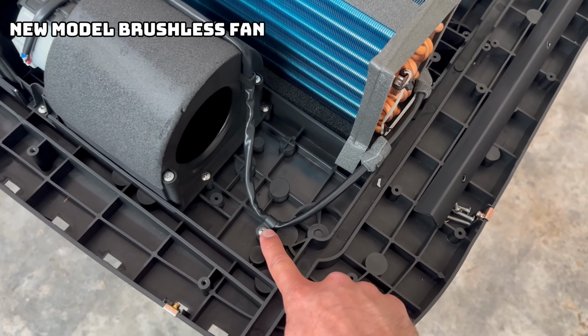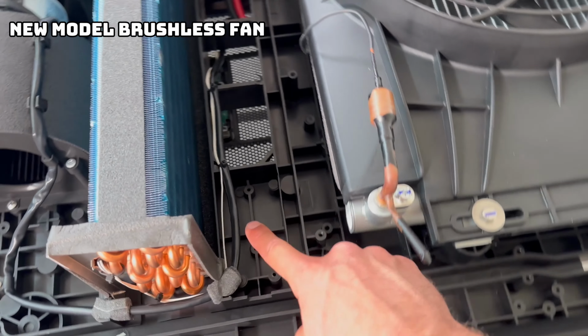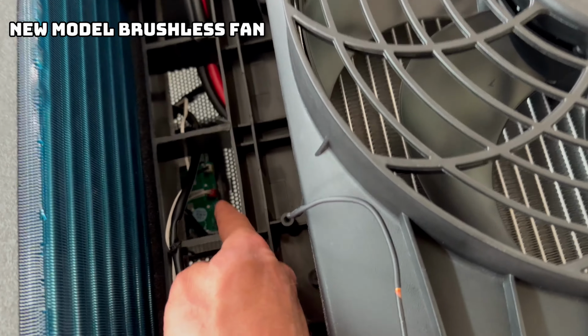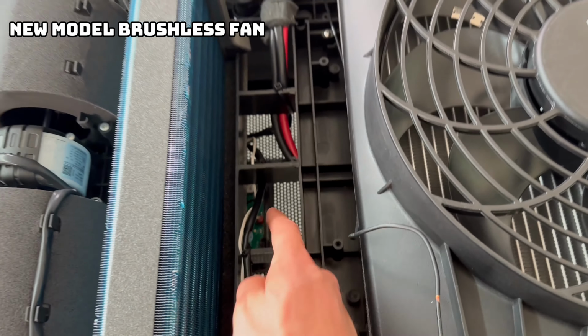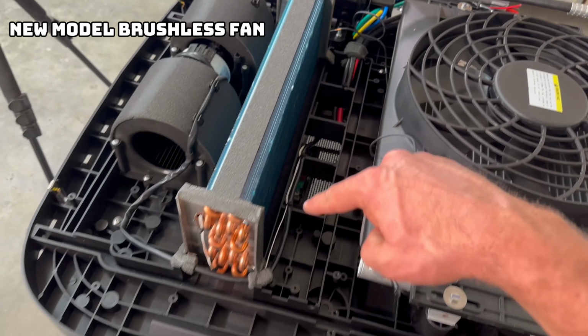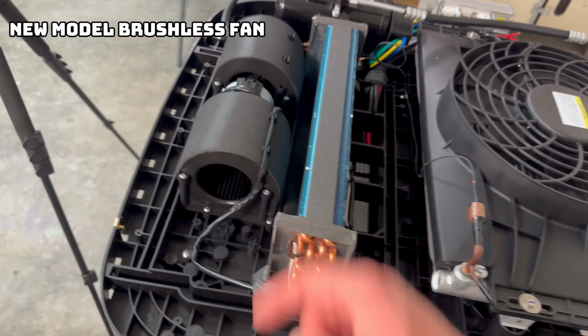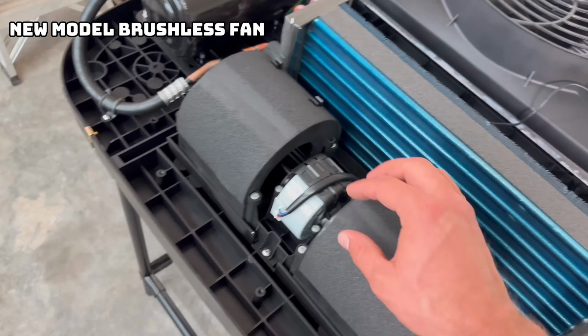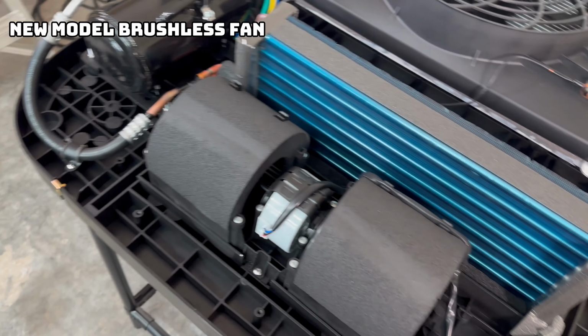And here I'll give you a better look at the wiring. It's held in place with these cable clamps, and it simply runs around and is zip tied and then goes down inside the unit to the control panel where it plugs in. So you will have to reroute this wiring if you end up replacing one of the brushless fans, because again, there's no connector up top to be unplugged.